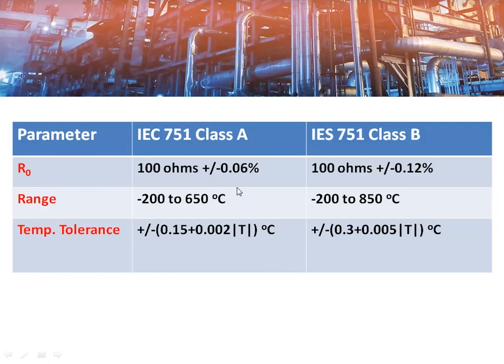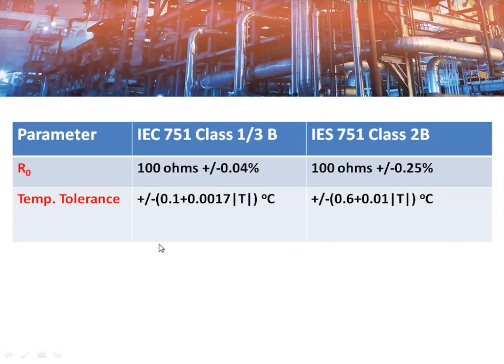Here you can see in this table the Class A and Class B defined as per the IEC standard and their parameters. R0 is the resistance at 0°C — for Class A it is plus or minus 0.06%, and for Class B it is plus or minus 0.12%. These are the temperature ranges for these classes. The temperature tolerance is not fixed — it increases with increase of temperature.